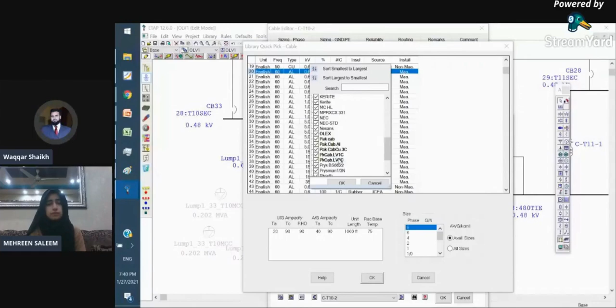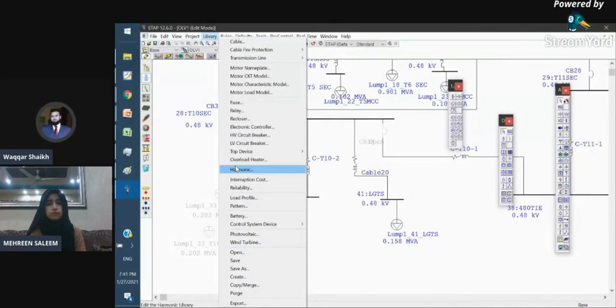So the best and easiest way is to go into the ETAP library option, then the cables option. There are two approaches. One approach is to make the cable from scratch. It will be very time consuming. Making a cable from scratch means you are not using any of the existing information. So it's always advisable that you do not make a cable from scratch, from zero level. Just fine tune one of the existing cables to the cable you want to make.